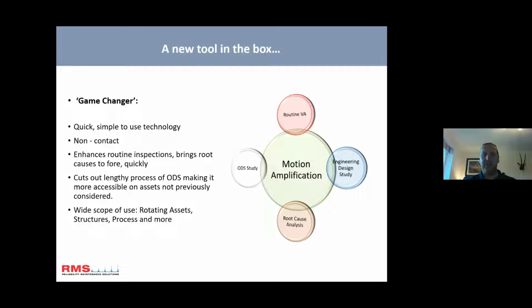It really sits alongside your routine vibration surveys, if they're picking up problems with 1 times running speed and other frequencies that aren't easy to diagnose sometimes, it's not always unbalance, it's not just alignment. A lot of the problems are actually base problems which show up at running speed. It's great for engineering design and root cause work, like the ODS study we mentioned. It's also really good for commissioning, when you get new kit on site you can scan it with the camera, check not just the machine but the instrumentation attached and the pipework, which gives you a good feel for what that machine's doing. So for me, it sits in really nicely with your existing PDM teams and condition monitoring setups.